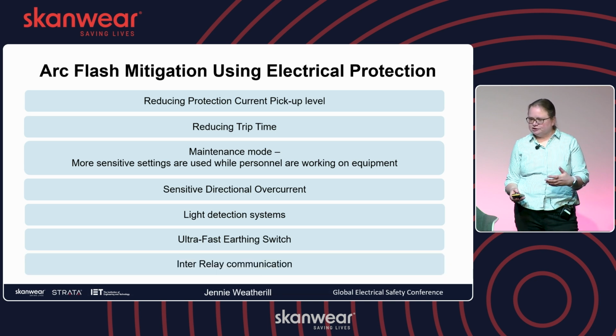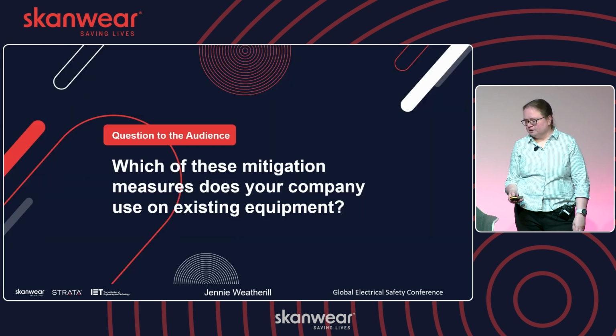Inter-relay communication, like GOOSE messaging and things, you can now have a relay say, I've got it, you don't need to go, and things like that. You can actually effectively remove the need for coordination, because you can put everything instantaneous and just get them to talk to each other. So these are things you can do, and the technology's there.